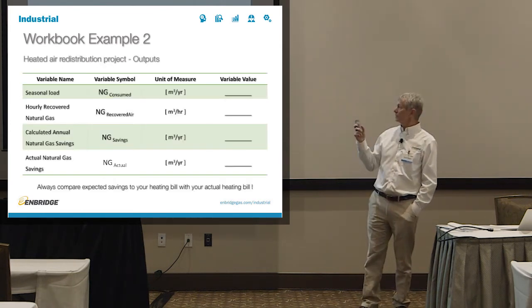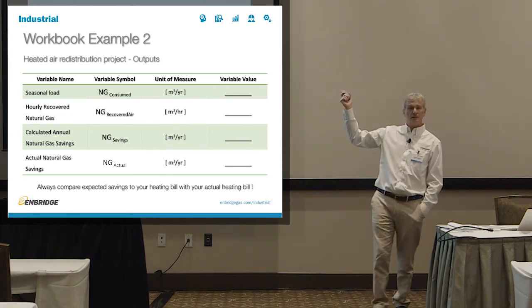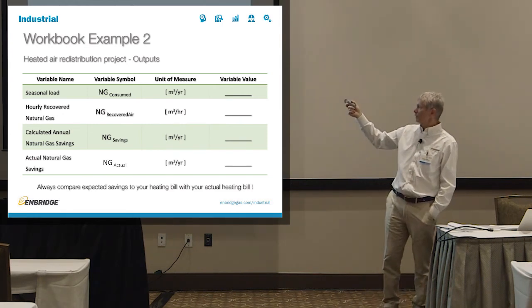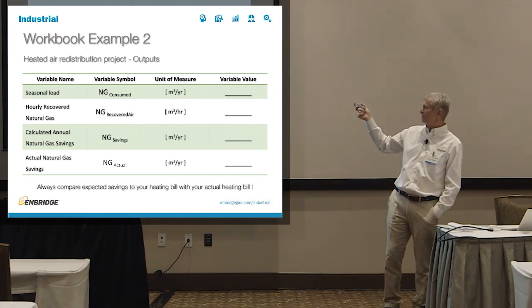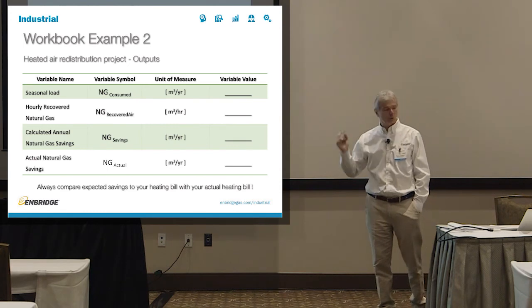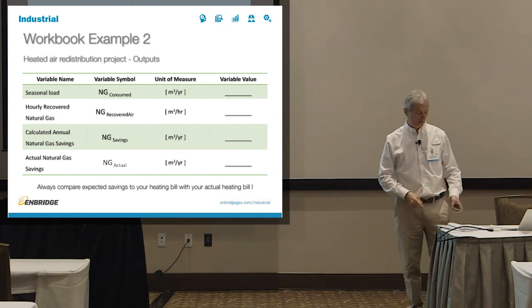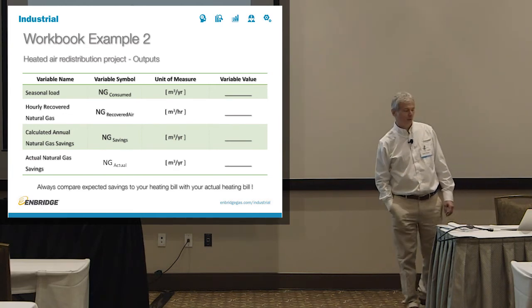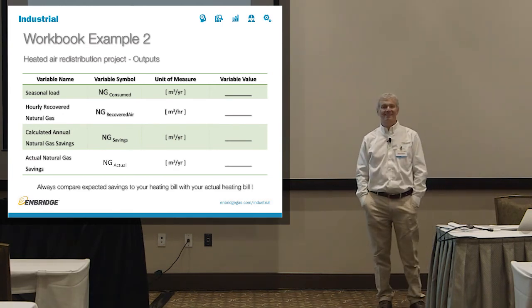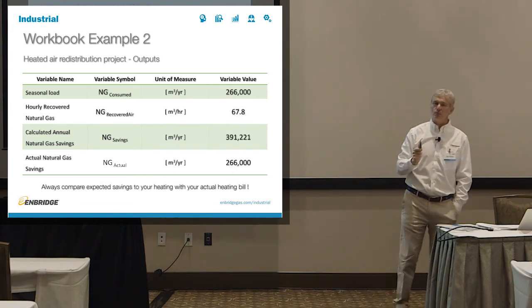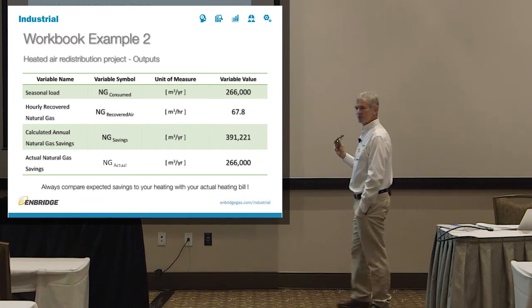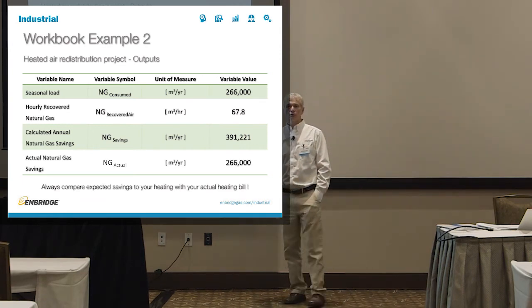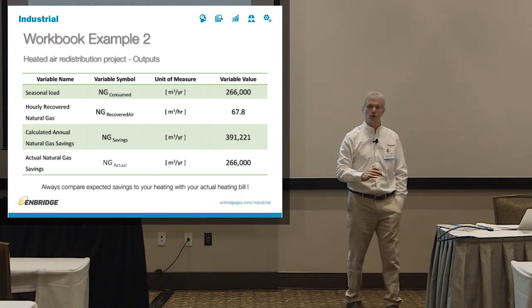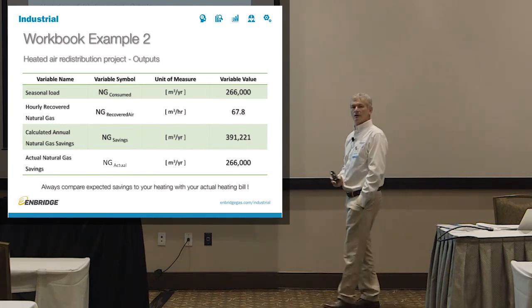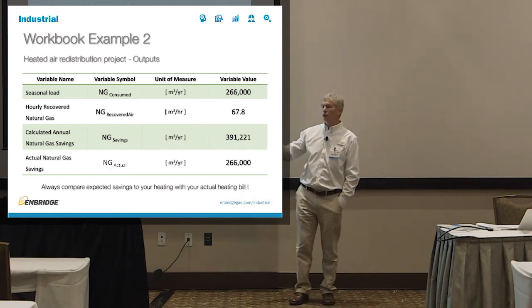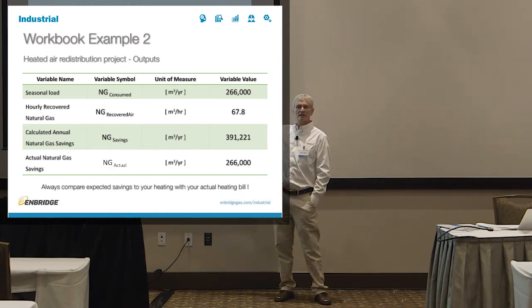So we will see what the seasonal load is. That's just 266,000 cubic meters, the first one. We'll want to see how much natural gas energy we recovered, and we see what the savings are. So we'll give you 5 minutes. And again, those who are first and accurate will get a reward. Correct. And this is one of the important points. The reason I chose this example is because a lot of vendors will come to you and say, I have this new technology, it's going to save you 400,000 cubic meters. And it might. The problem is if you're only using 266,000 cubic meters, that's the maximum you can ever save.